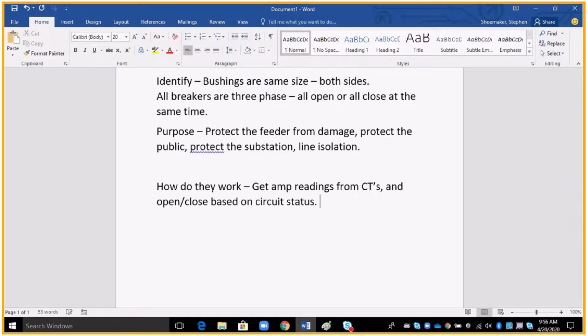Remember, this is all automated. This is all happening without human intervention. Now you can take control, and we'll talk about that in just a moment, of the breaker. So you can do functions inside of it, opening it and closing it. But as far as an energized line is concerned, they're automated, and there's no further than you need to go as far as that is concerned, unless you need to open a breaker. Okay? You as a lineman can open only.